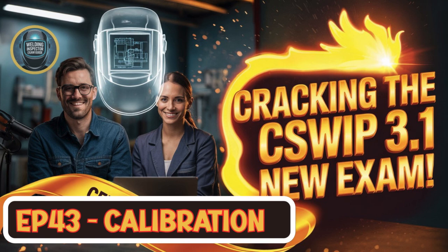It stands to reason that the tools you use to check your welding equipment need to be even more precise, right? What are the requirements for these calibration instruments? Can I just grab any old multimeter off the shelf? Definitely not. These instruments have to be calibrated themselves by a recognized calibrator. And they need to use standards that are traceable back to a national standard.